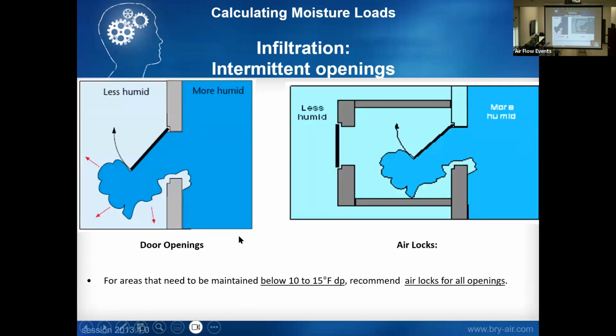So one of the ways we combat door openings per hour in a more critical space that needs to be held at a critical condition at a lower dew point or RH is we build in what we call an airlock, which is basically a small room vestibule, so to speak, that has two doors. And typically those doors are interlocked. So someone will open the outside door from the more humid space, that door will close, it senses the door is closed. And a lot of times they gotta be in that airlock for a certain period of time, typically about a minute, before that second door allows them to open. Now, there's emergency things, so if you got an emergency exit, you can exit and bypass the timers, but that is a way to combat the infiltration of door openings per hour.